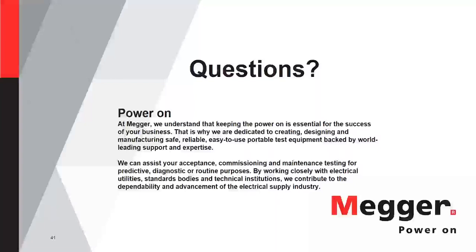How is battery continuity verified specifically, and does it require removing the battery from service? Now, the batteries do not have to be removed from service. If you want to do a direct measurement of battery continuity, keep in mind what continuity basically is saying: that I can get current through this string. Okay, I have a continuous path. If you're using the BITE 2, it's very simple, because when you hook up, the transmitter injects a 10 amp signal through the entire string, and it doesn't have to come offline to do that. So that's actually part of that test. That's probably the easiest way to verify that.